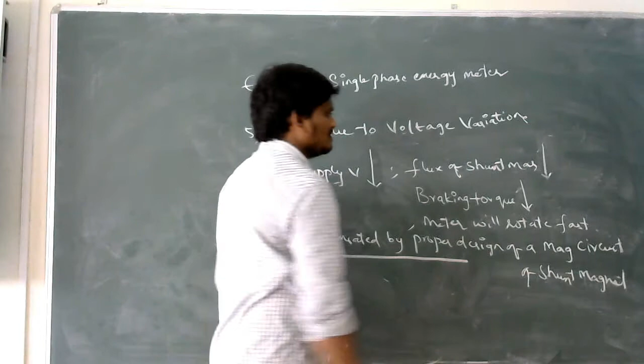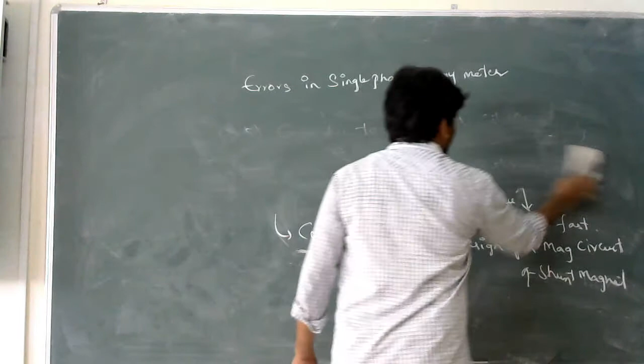So in order to reduce the error due to the voltage variation, that is either it will increase or decrease, you need to have a proper design of the magnetic circuit. That is, supply voltage should have only a minimum impact on the shunt magnet. This is regarding error due to voltage variations. Coming to the next type of error, that is temperature error.